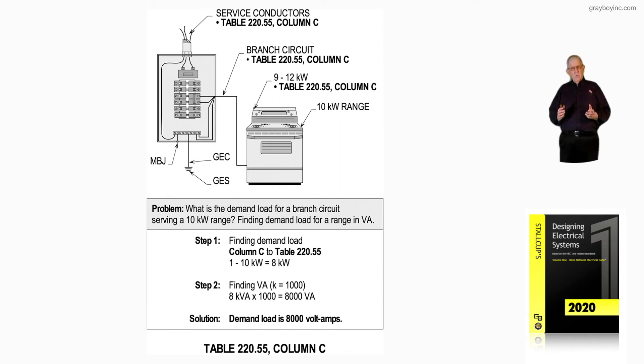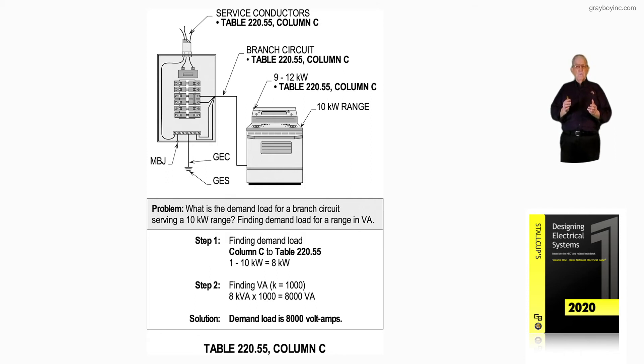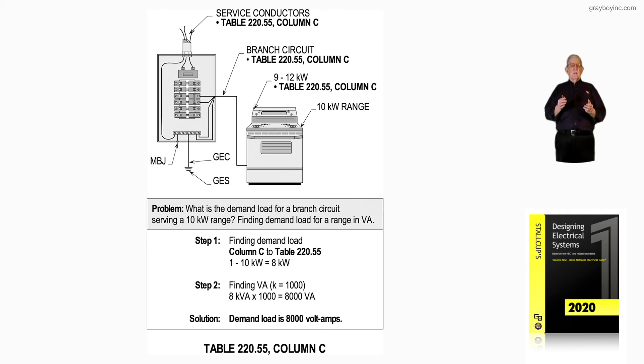This was a proposal stating that VA is more accurate than KW, because where there is not strictly resistance, more values make up a circuit — such as capacitive reactance, inductive reactance, and all that kind of thing. So step two is just taking the KW and making it KVA, then multiplying by 1,000 to get the VA rating of 8,000 VA. So the answer for the demand load from Column C of Table 220.55 is 8,000 VA.